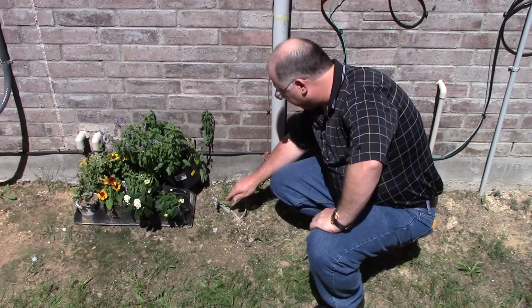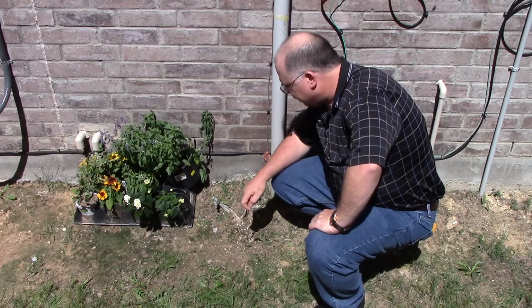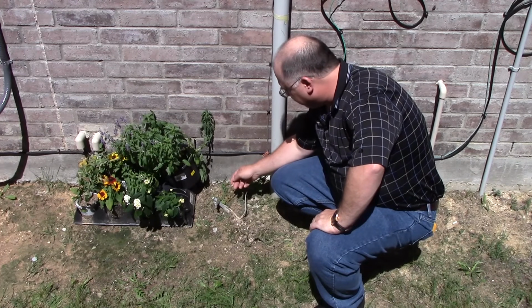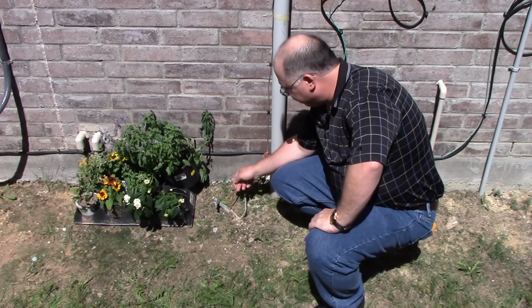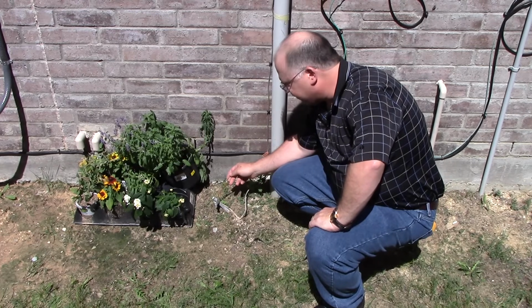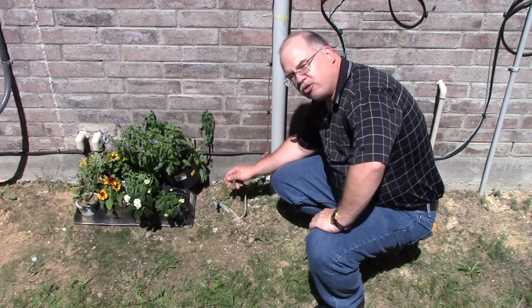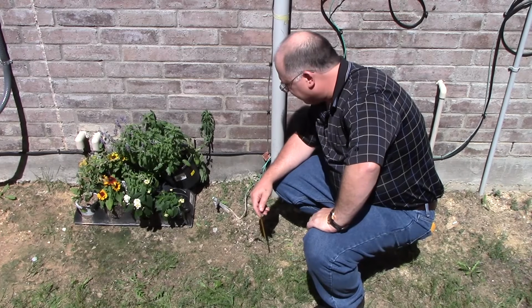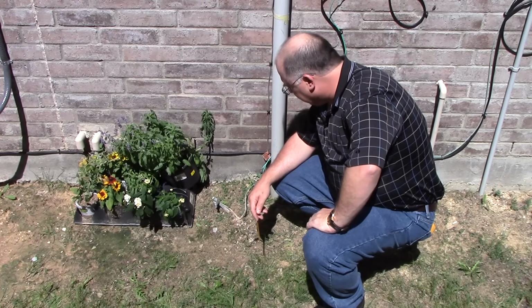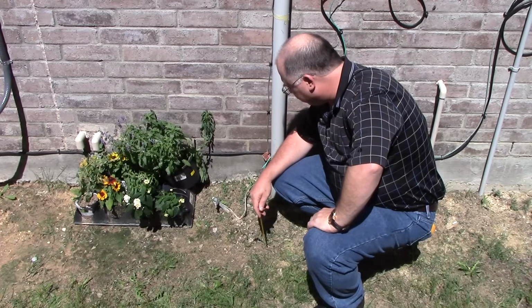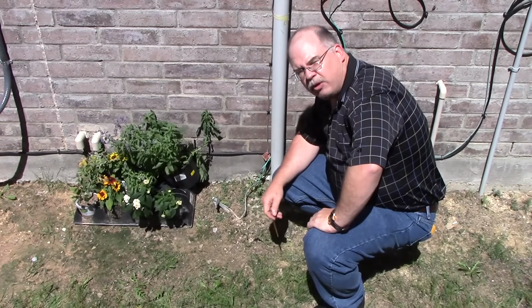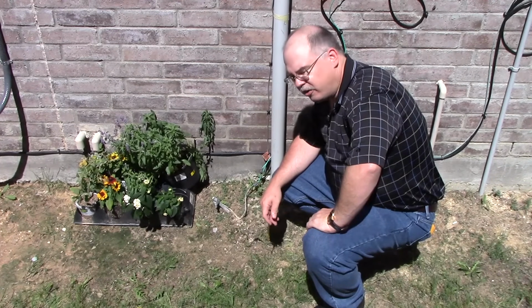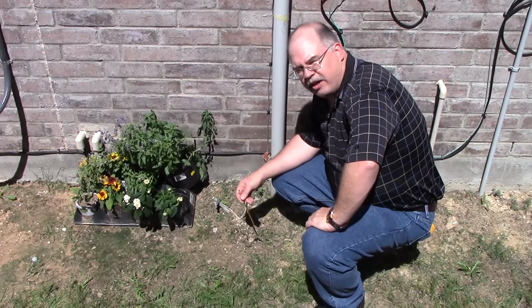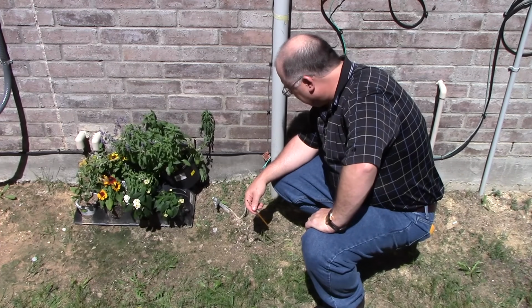This terminal right here, this lug, is actually rated for direct burial, so that is not an issue. They do have it installed correctly, whereas they have the grounding electrode conductor coming up through the back side of this acorn clamp and not on the screw side, so that's good that they have it that way. So in this case, it is driven at an angle. It's not required, so I wouldn't even worry about it as much as a home inspector. It is extra, it is additional there. It's certainly not going to hurt anything. So I'm just making sure.